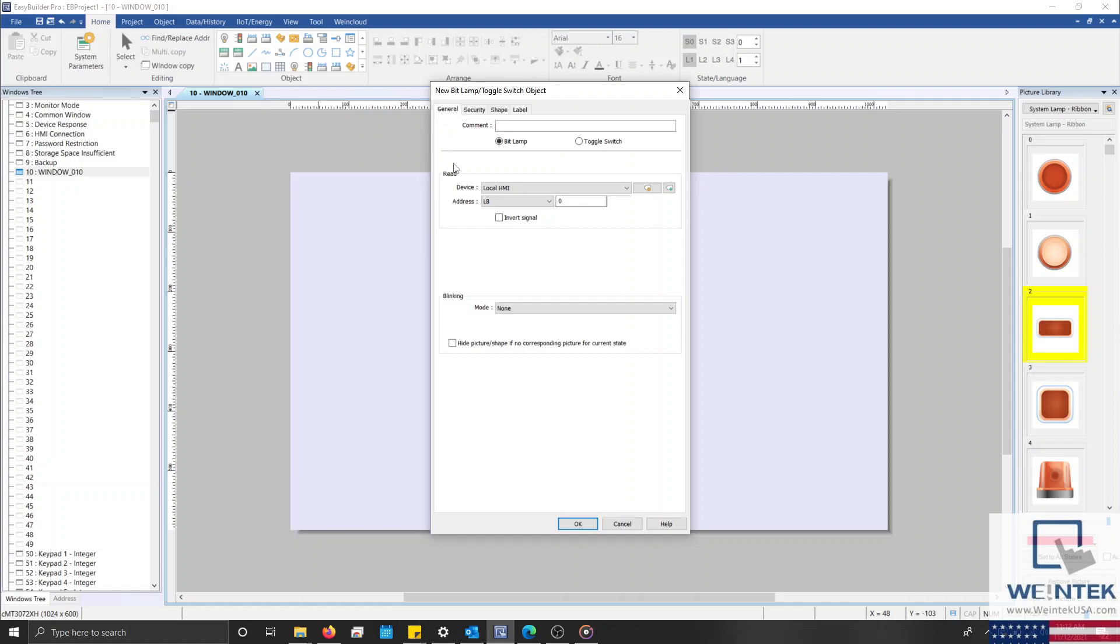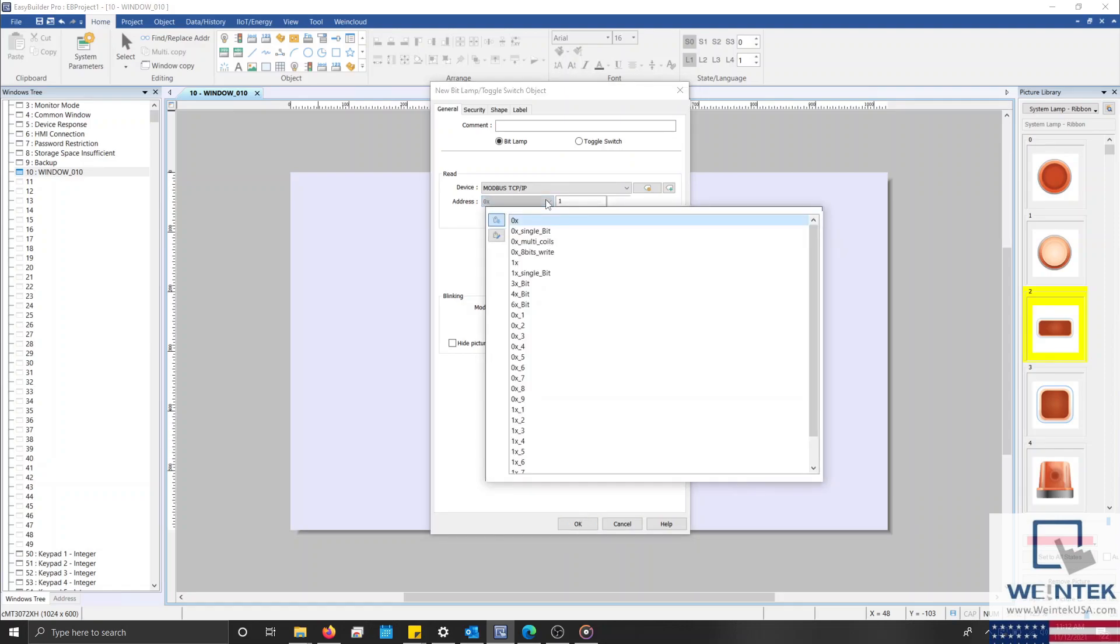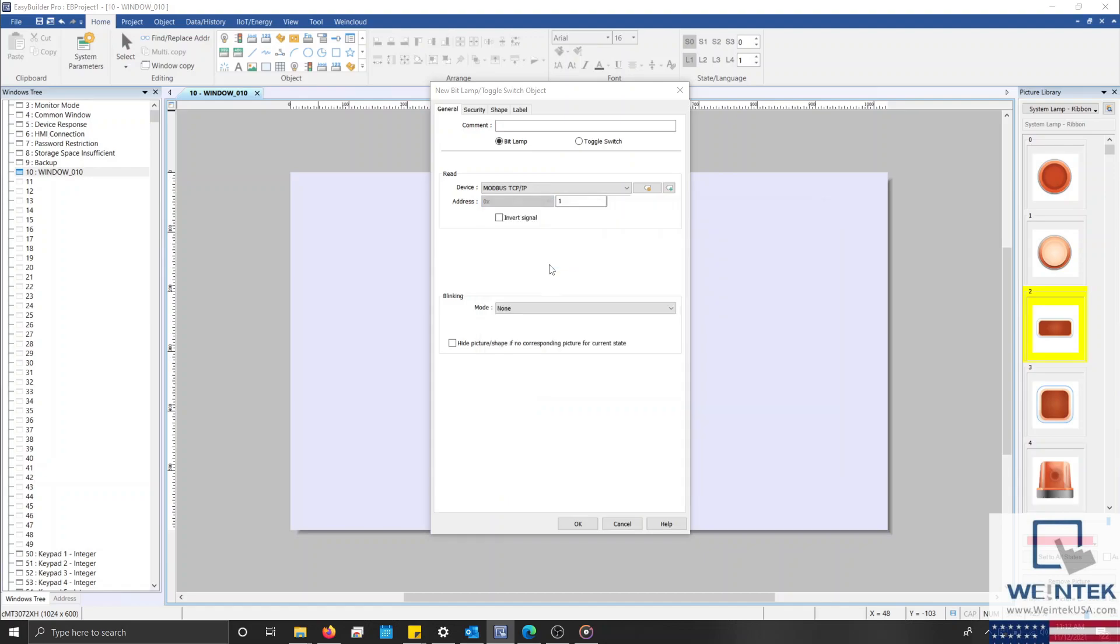To address this Bitlamp to a register within my Modbus device, I'll select the Device drop-down list and choose my Modbus TCP IP device. Next, within the Address or Address Type drop-down list and text box, we can specify the location within PLC memory that this object will reference. In some applications, it may be necessary to modify an HMI's system tag, access a user-defined tag, or assign an index register as well.